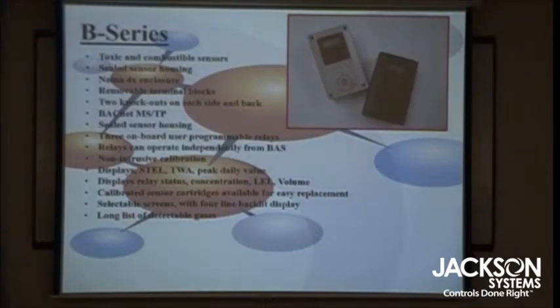The relays on it can also be controlled by a BACnet controller independent of gas concentration. So if they have other parameters that they want to check and activate relays or something locally, they can use the relays on the BACnet sensor. So it makes it very, very convenient. With a BACnet sensor, you don't have the 4 to 20, but you have all the relays. So if you want a BACnet sensor, it's because you're going to connect it to a BACnet controller.